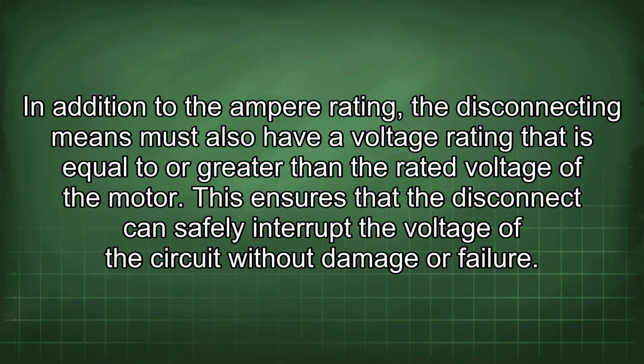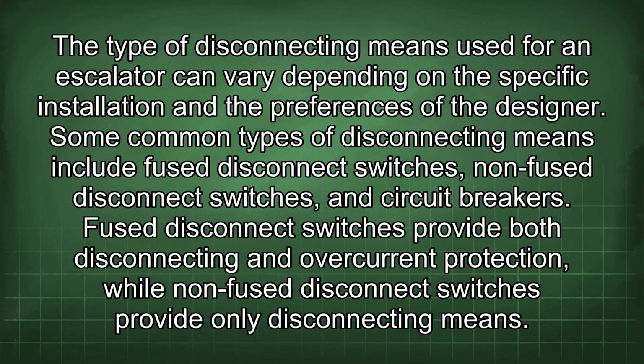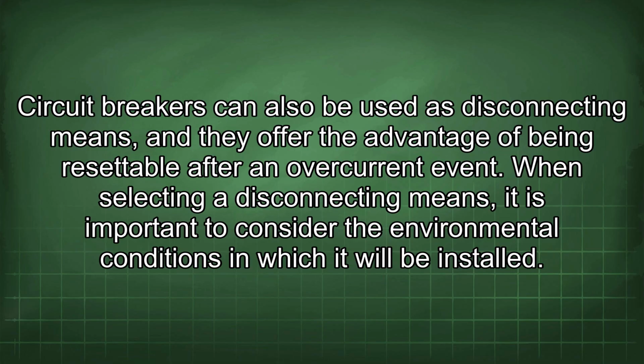In addition to the ampere rating, the disconnecting means must also have a voltage rating that is equal to or greater than the rated voltage of the motor. This ensures that the disconnect can safely interrupt the voltage of the circuit without damage or failure. The type of disconnecting means used for an escalator can vary depending on the specific installation and the preferences of the designer. Some common types of disconnecting means include fused disconnect switches, non-fused disconnect switches, and circuit breakers. Fused disconnect switches provide both disconnecting and overcurrent protection, while non-fused disconnect switches provide only disconnecting means. Circuit breakers can also be used as disconnecting means, and they offer the advantage of being resettable after an overcurrent event.